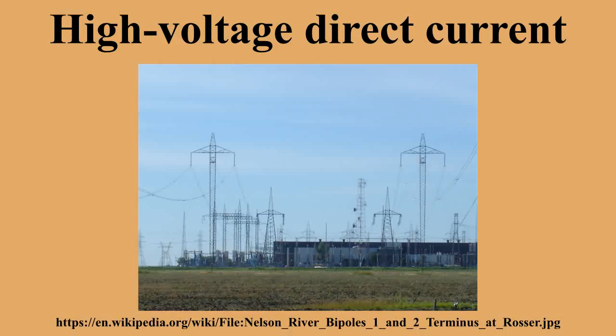By way of comparison, AC harmonic filters of typical line-commutated converter stations cover nearly half of the converter station area. With time, voltage source converter systems will probably replace all installed simple thyristor-based systems, including the highest DC power transmission applications. Advantages of HVDC over AC transmission.